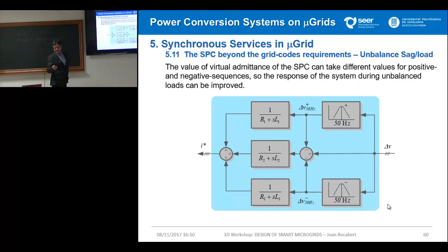This is the same in the case of an unbalanced sag or load. This is when you get an external short circuit at a remote point. Your voltage at the point of common coupling of your converter will be distorted like that. With the introduction of the SPC, we are able to restore, or at least to reduce a lot, the negative sequence of your voltage.